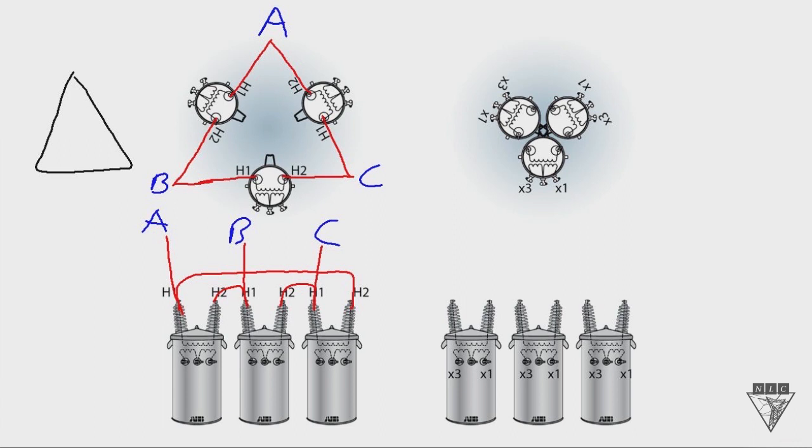With a delta connection it's a phase-to-phase connection. With transformers, in order to make them work you have to have a potential difference across the coil. You can do this in one of two ways: either a phase-to-phase connection or a phase-to-ground connection. So for a delta it's a phase-to-phase connection. Now let's move over to the secondary side.